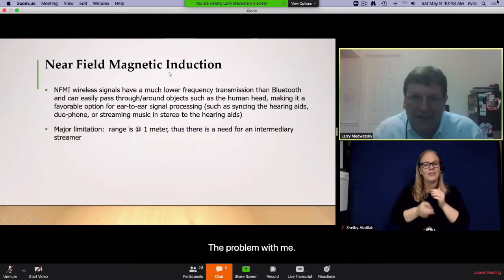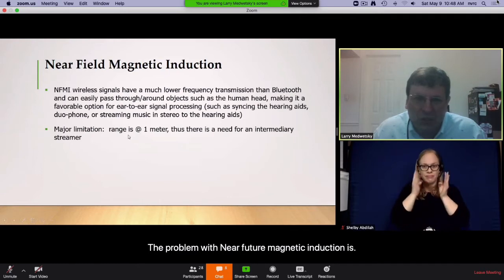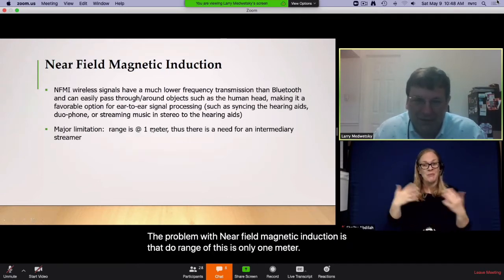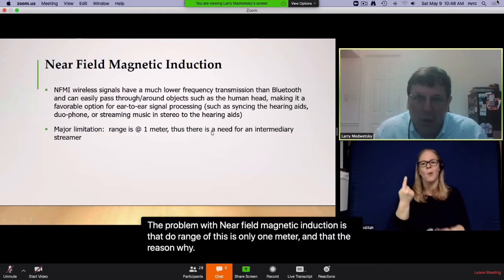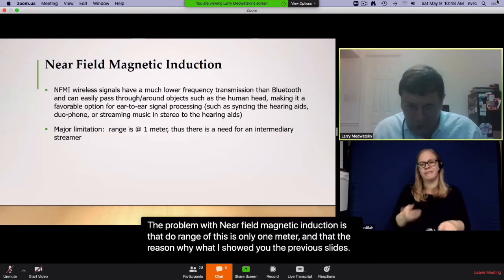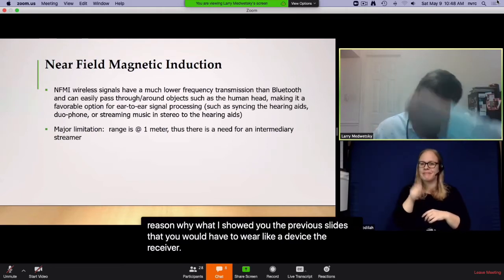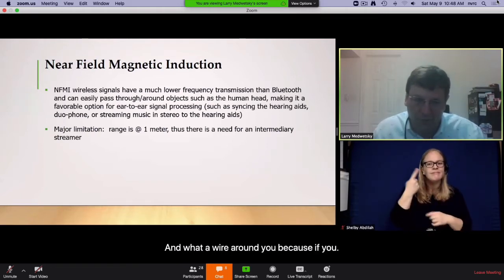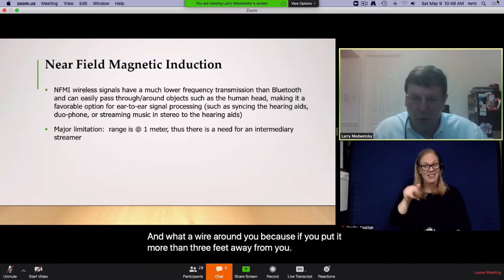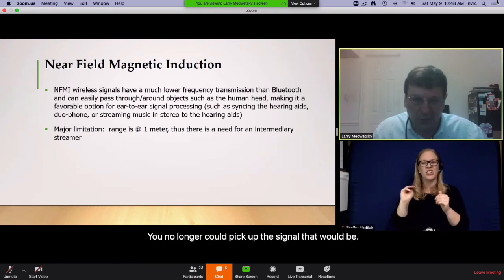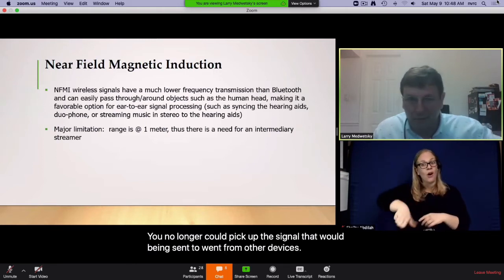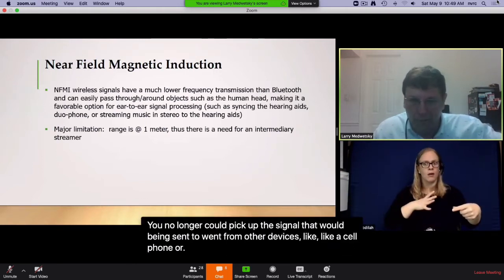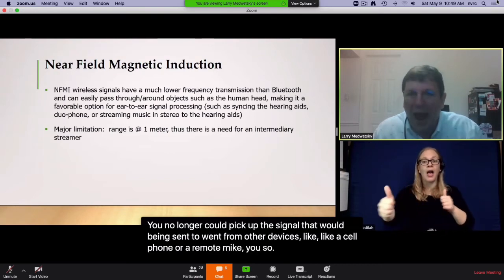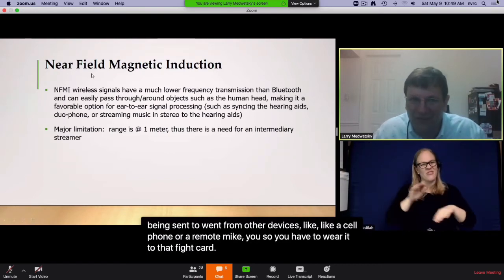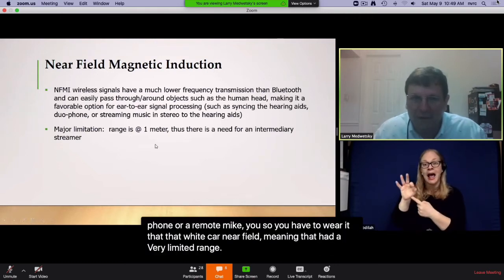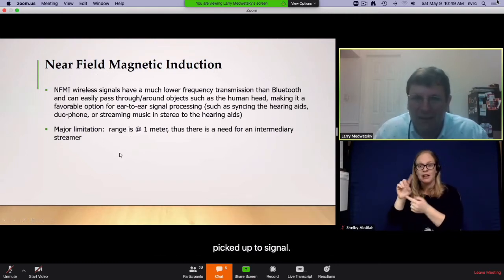The problem with near field magnetic induction is that the range of this is only 1 meter. And that's the reason why, as I showed you in the previous slide, you would have to wear a device, a receiver, with a wire around you, because if you put it more than 3 feet away from you, you no longer could pick up the signal that was being sent to it from other devices, like a cell phone or a remote mic. So you have to wear it. That's why it's called near field, meaning that it had a very limited range from which you could pick up the signals from the receiver or the streamer.